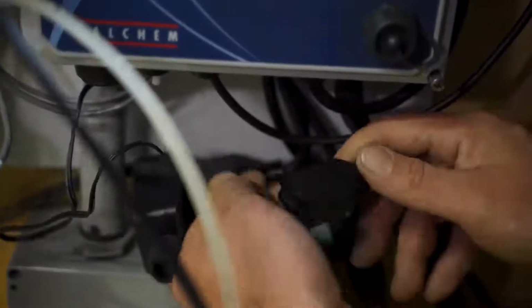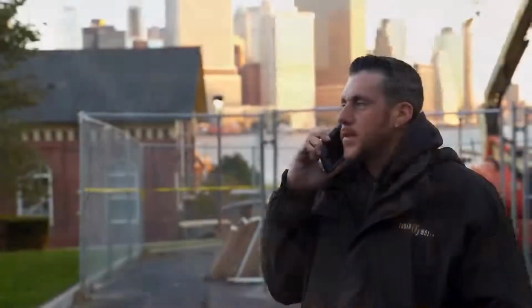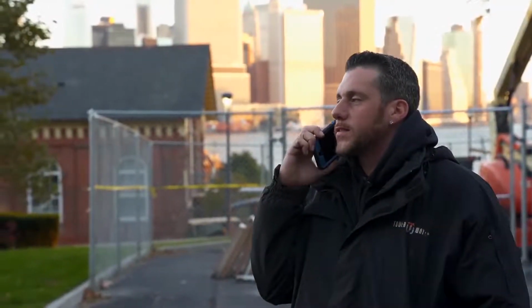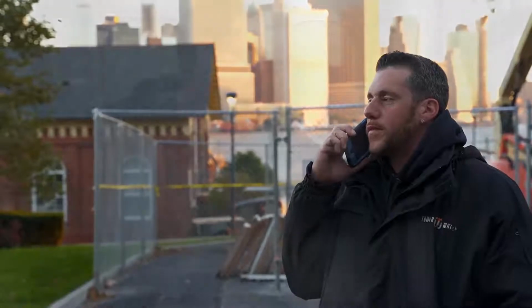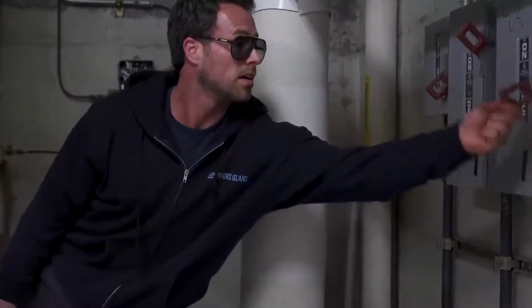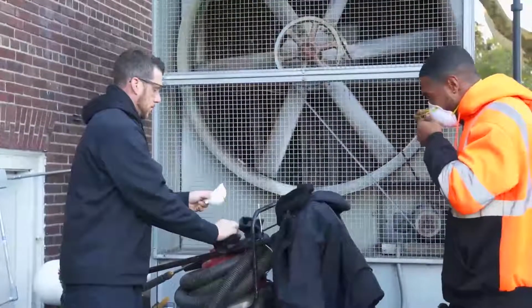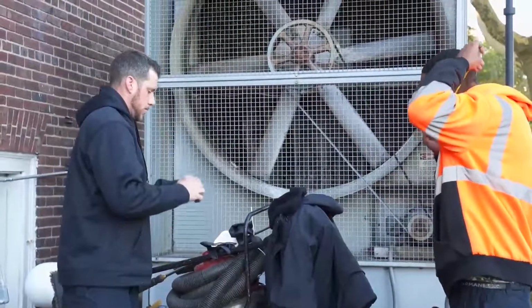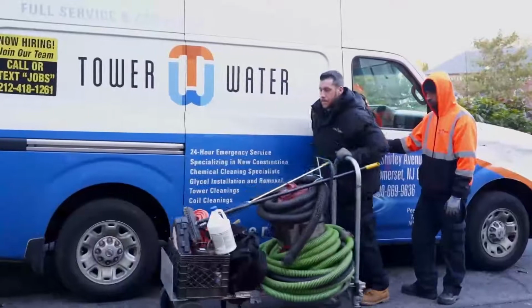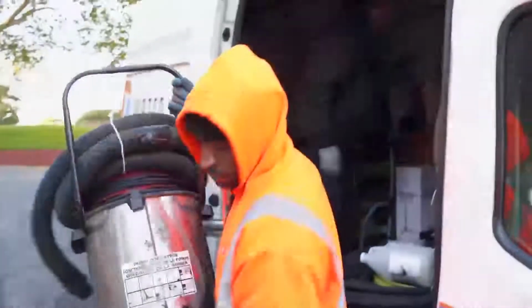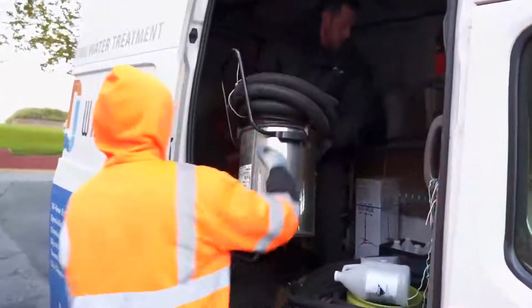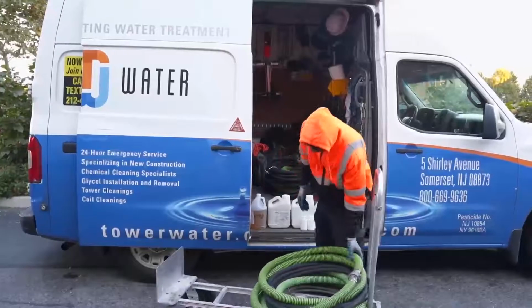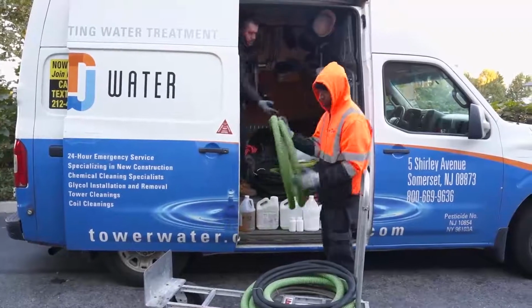After plugging the bleed valve in, call the customer, informing that you are getting ready to leave the site. Ask them to verify the entire system is operating correctly. Show them the closed disconnect for the fans and let them know that the fan should remain off for the next 6 hours so that disinfection can take place. Remain on site to watch that the system is operating correctly. Make sure you have secured everything and are prepared to leave the site.